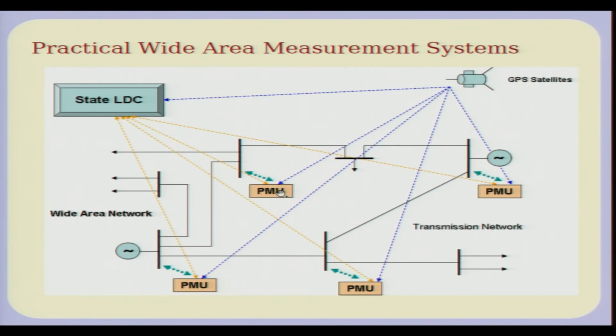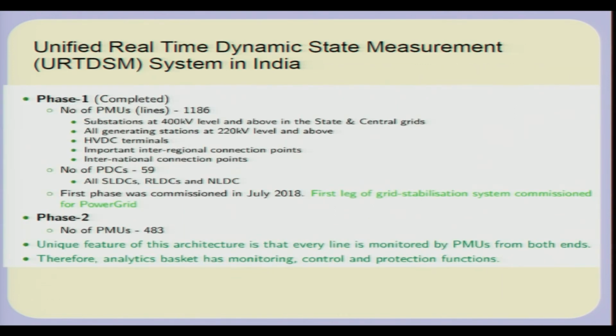So, that is a fairly high degree of accuracy, and because of that you can actually measure these phasors. These are all time synchronized phasors, and these can be sent to a load dispatch center. So, this is a practical wide area measurement scheme which is in fact being implemented in our country, and it is very useful in a synchronous grid.